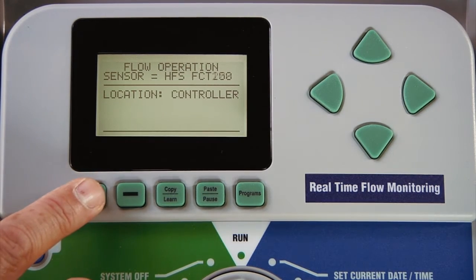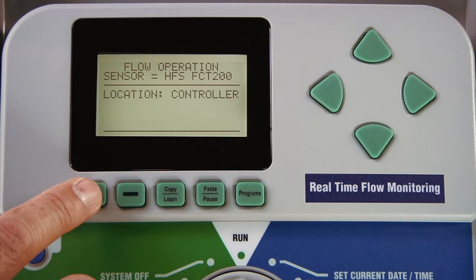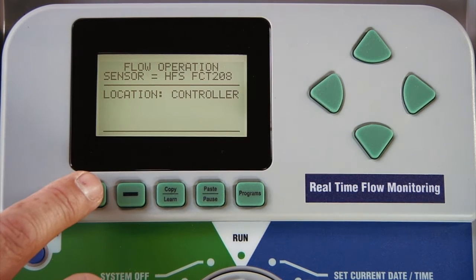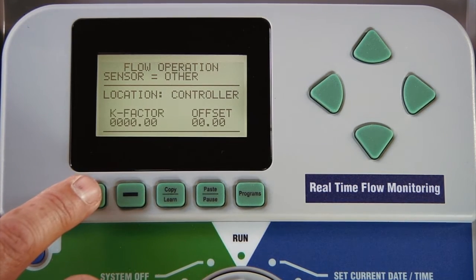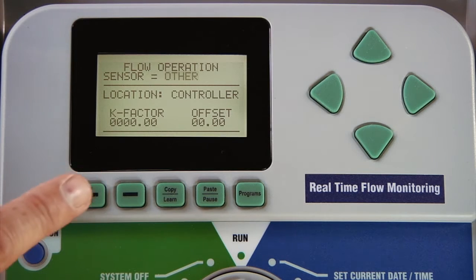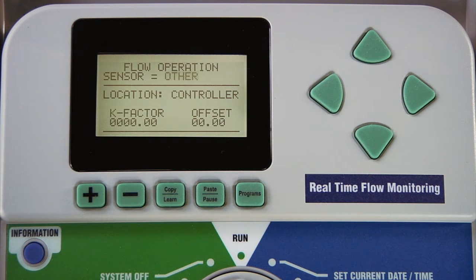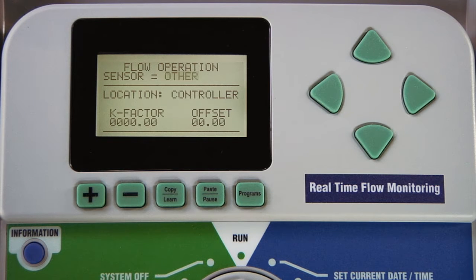Using the plus button, we can scroll through the Hunter flow sensor sizes as they're already in the face pack. At the end of the line, you can go to other if you have a Badger Meter or Data Industrial IR-220 series installed in the field. You will need to input the manufacturer's specifications for K factor and offset manually.